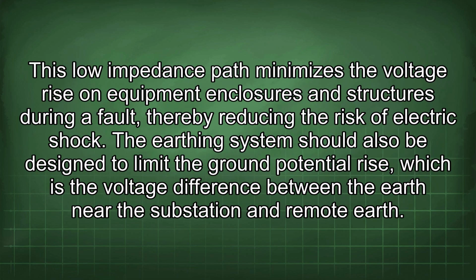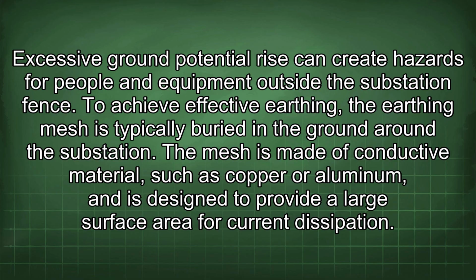This low impedance path minimizes the voltage rise on equipment enclosures and structures during a fault, thereby reducing the risk of electric shock. The earthing system should also be designed to limit the ground potential rise, which is the voltage difference between the earth near the substation and remote earth. Excessive ground potential rise can create hazards for people and equipment outside the substation fence.